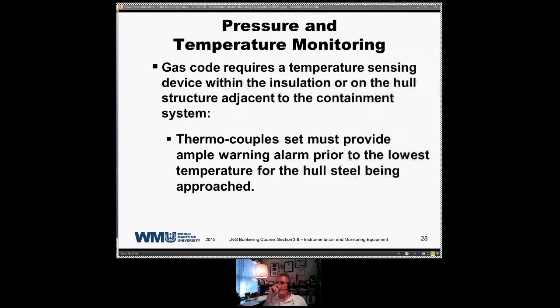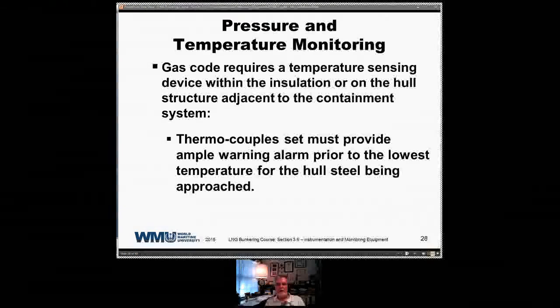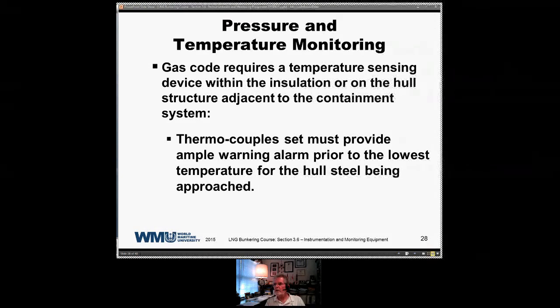Gas code requires a temperature sensing device within the insulation or on the hull structure adjacent to the containment system. Your hold spaces, secondary barriers, and insulation spaces are all going to have temperature sensing devices. You don't just put one of these tanks together and say everything is going to be fine. There are numerous temperature sensing devices placed throughout the secondary barrier, the primary barrier, and the hold space, and these are monitored at all times.